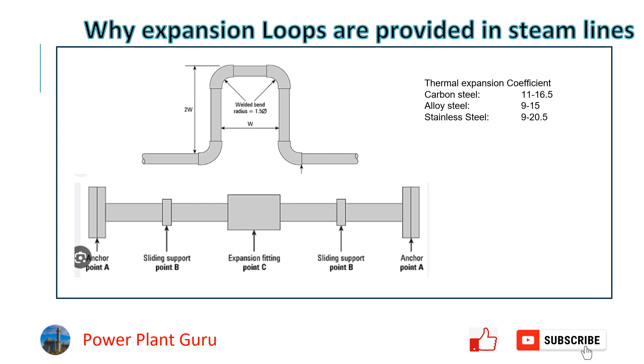We know that before boiler start-up, the temperature is around ambient — around 35 to 40 degrees. When the boiler starts, the main steam line temperature heats up and goes up to 550 degrees. So there will be around a 500-degree rise, and we need to accommodate the thermal expansion due to this temperature difference.